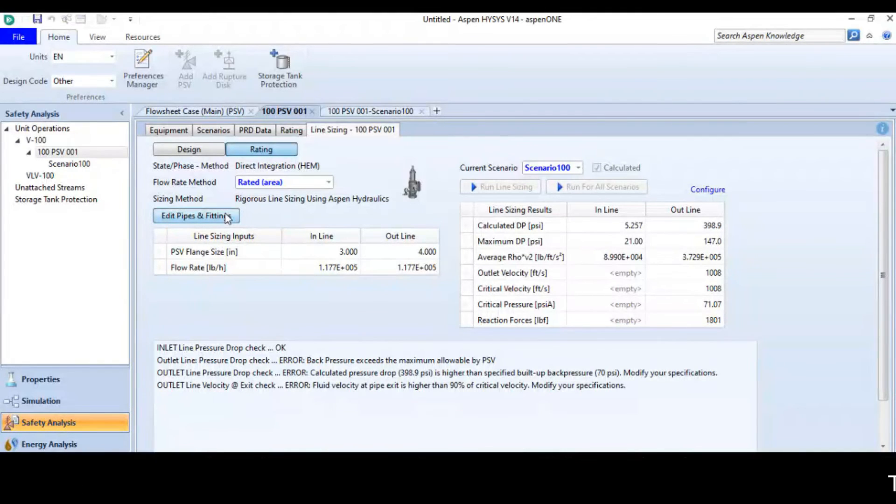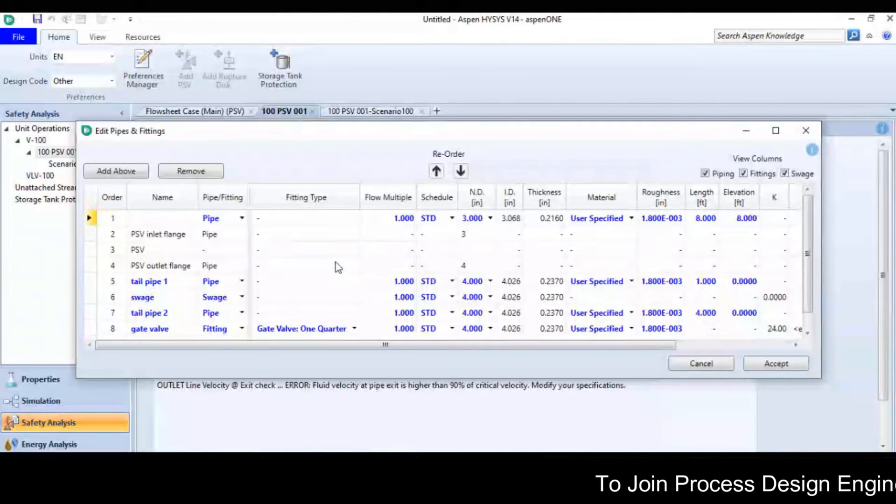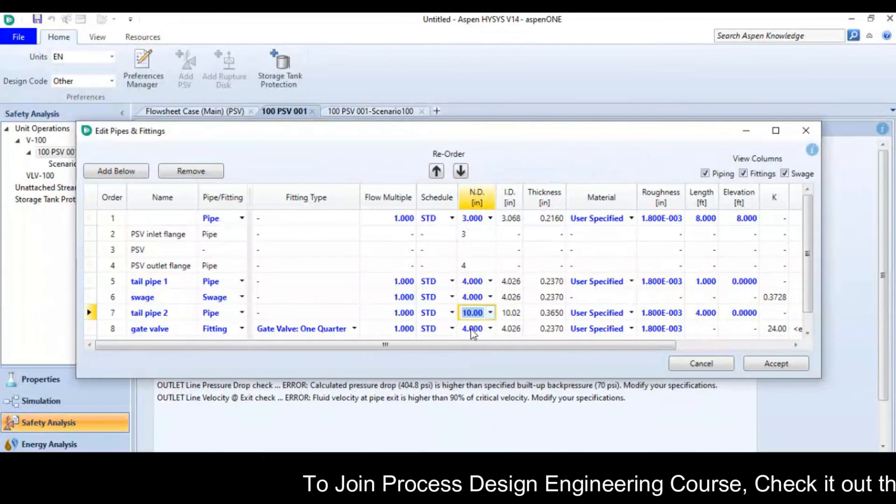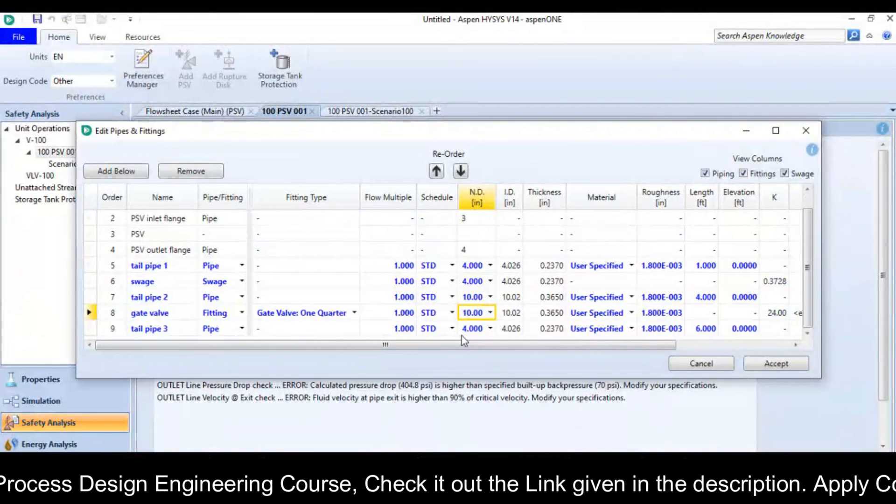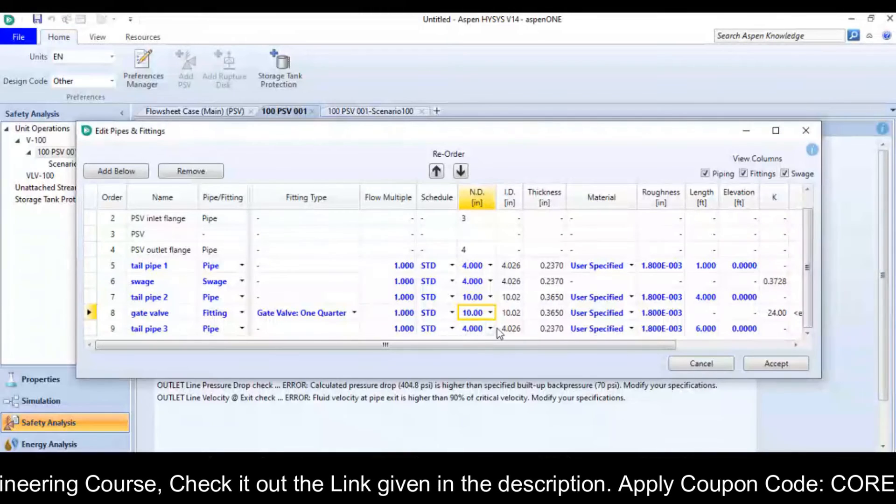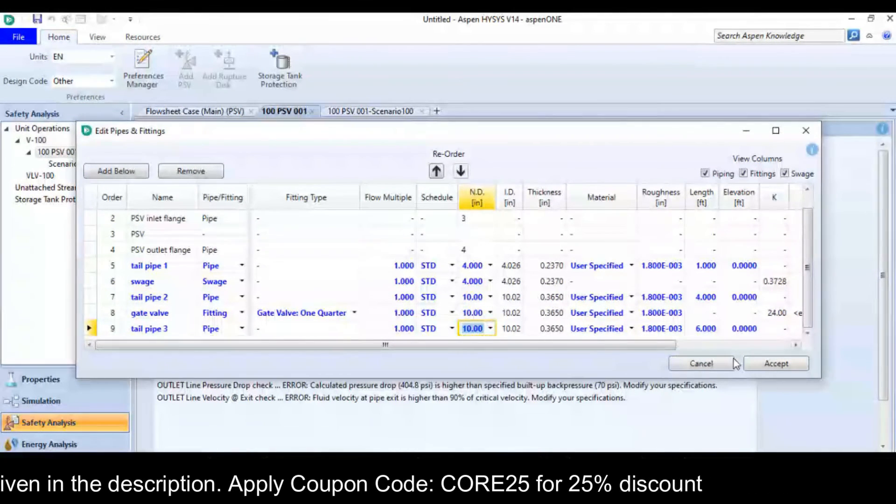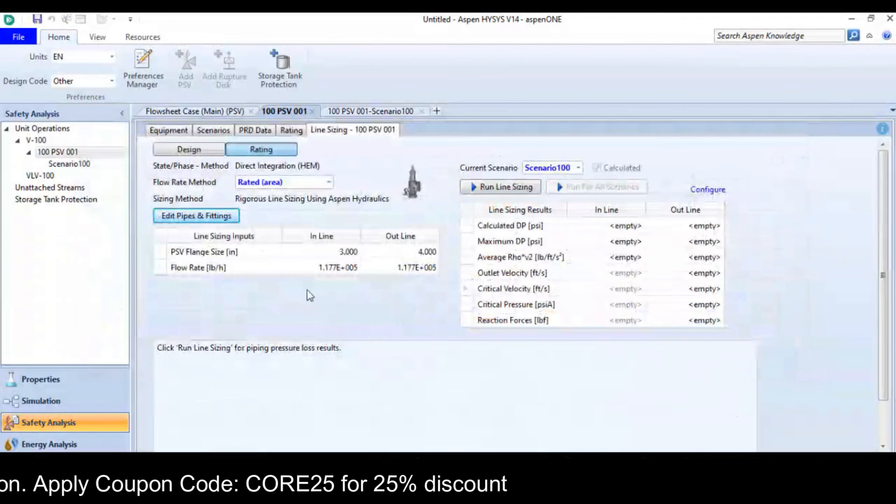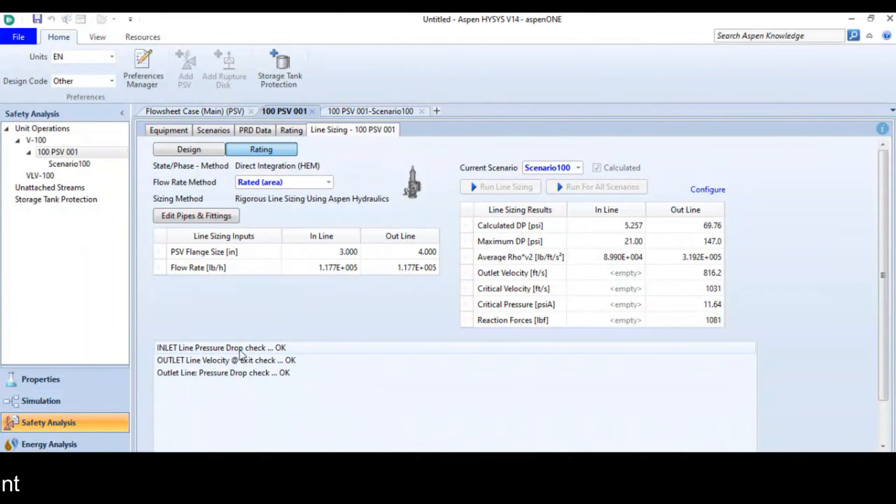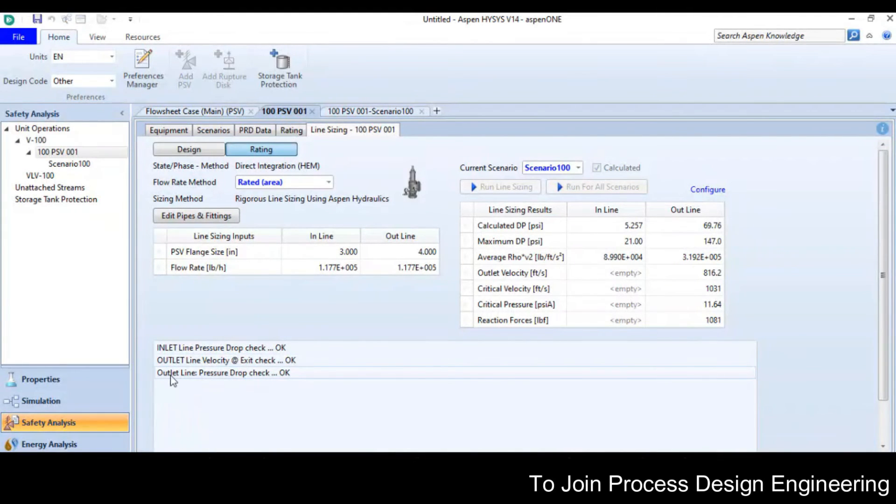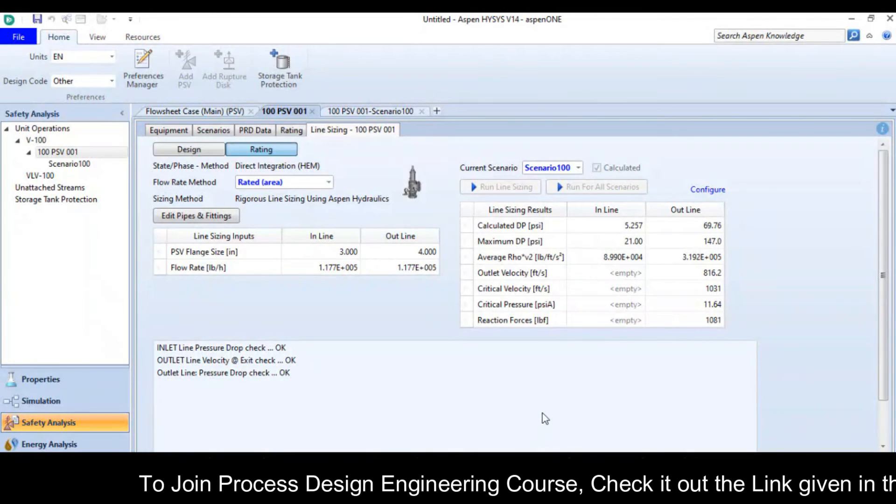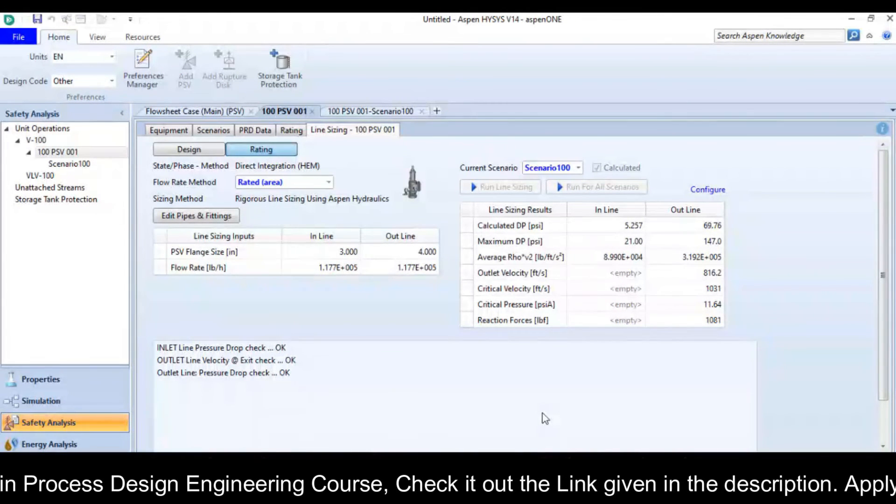So in this particular case, I will go to edit piping and fitting, the tailpipe 2 is 10 inches and the gate valve is 10 inches and the tailpipe 3 is also 10 inches. Now I will try to run this scenario. You can see that the inlet line pressure drop check ok, outlet line velocity check ok, outlet line pressure drop check ok. So it is successfully completed.